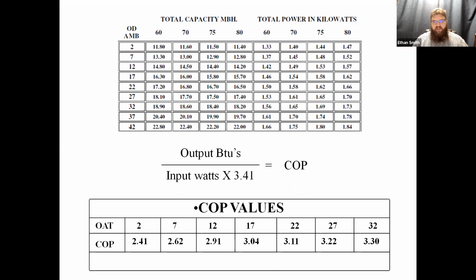So just as an example, guys, I did this for my system that's outside my house right now. With my current gas prices and my current electrical rates, my gas is so darn cheap that, back to the beginning of the class where I mentioned it, my unit is more economical to run on the heat pump above 35 degrees and the gas furnace below 35 degrees. That's how I arrived at that number. I did my break-even COPs for my natural gas and determined that at about 35 degrees, I crossed the threshold from more efficient on my natural gas to more efficient on my heat pump. In years past, when natural gas was significantly more expensive, my break-even COP landed me right around 15 degrees.